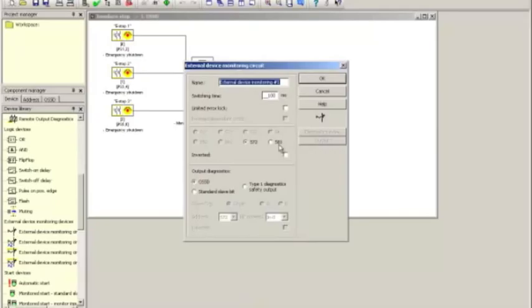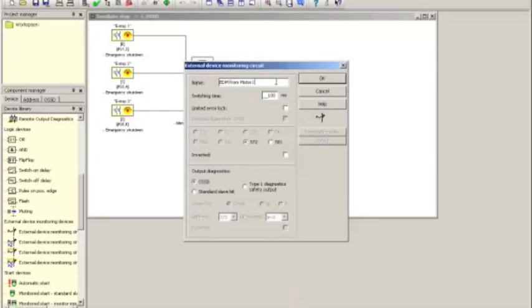Now what you can see there is you can name the device. I can call this EDM from motor one, for instance, and I need to provide a switching time. The default switching time of 100 milliseconds is a little too aggressive for my taste for most contactors.